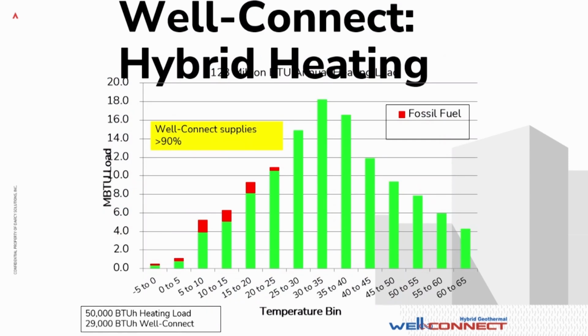So here's an important chart. If you look at the bin data, this is actually modeled off of Buffalo, New York, and you look at the total BTUs at each temperature bin throughout the heating season. This is an example of a house that Manual J would say is a 50,000 BTU load. We put our 2.5 ton geothermal unit in there, and we're doing over 90% of the heating throughout the winter. So what you see there in the green is our Well Connect geothermal heat pump, and the red is the supplemental propane. So that furnace is still sitting there, and it's there just for those coldest days.